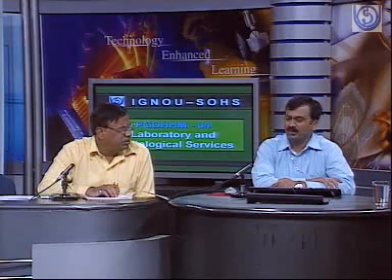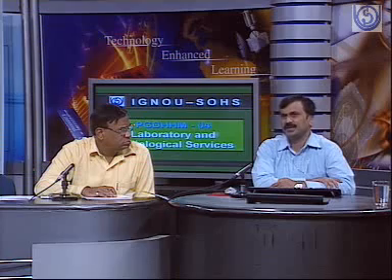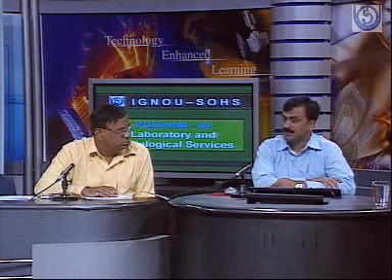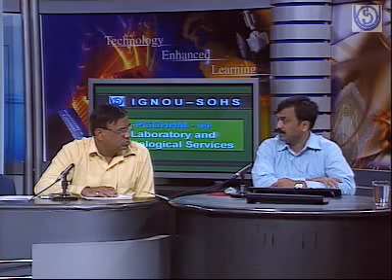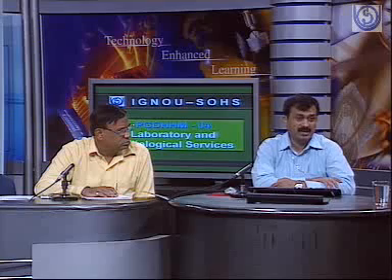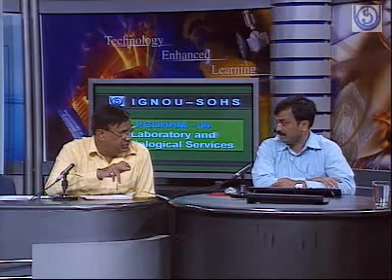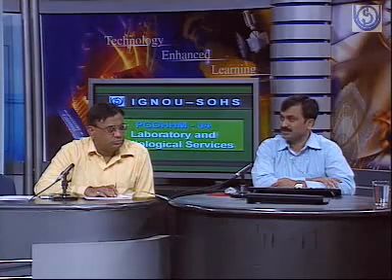Whereas in hospitals where normal X-ray installations are there, they are RSO grade 1, that is your radiologist who is trained in radiation safety and certified by AERB. That is very important. Most of the hospitals actually forget to get them certified through AERB, that they have taken the training and they are certified. Is it mandatory? It is a mandatory requirement as far as AERB is concerned.